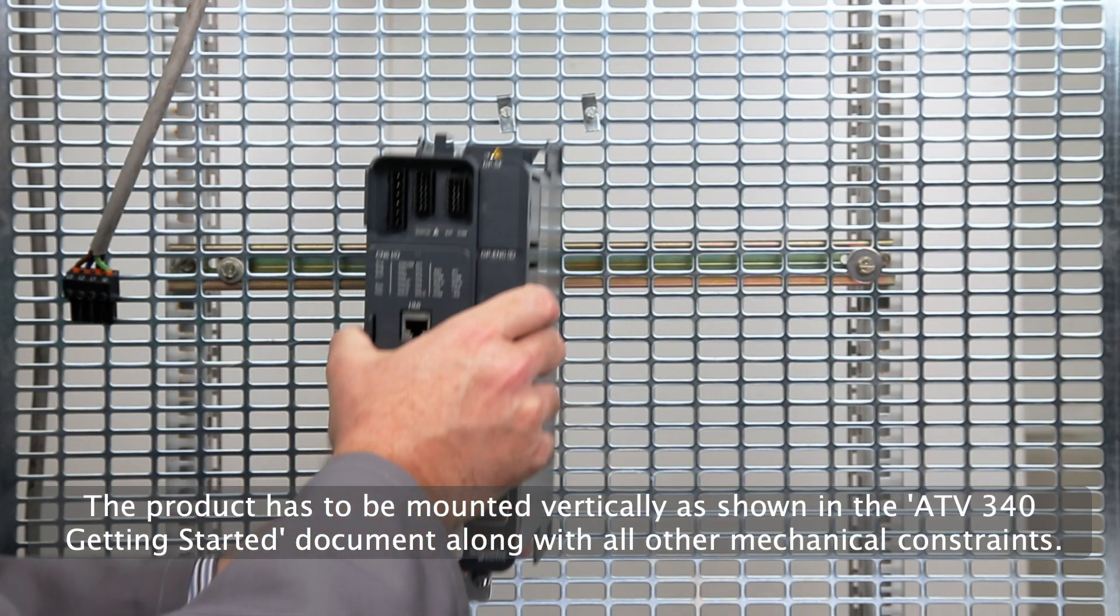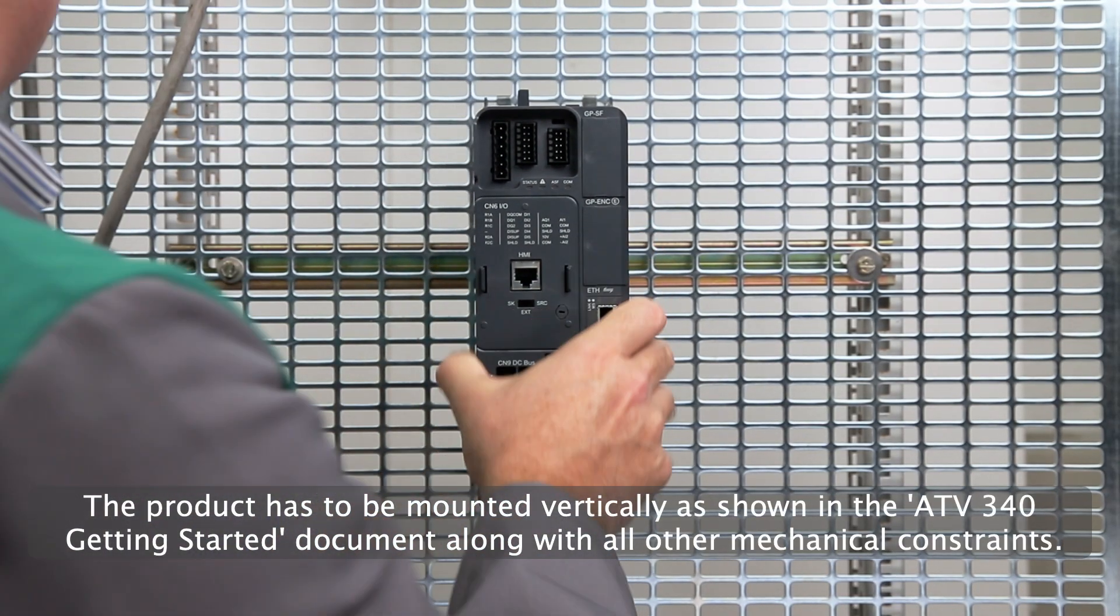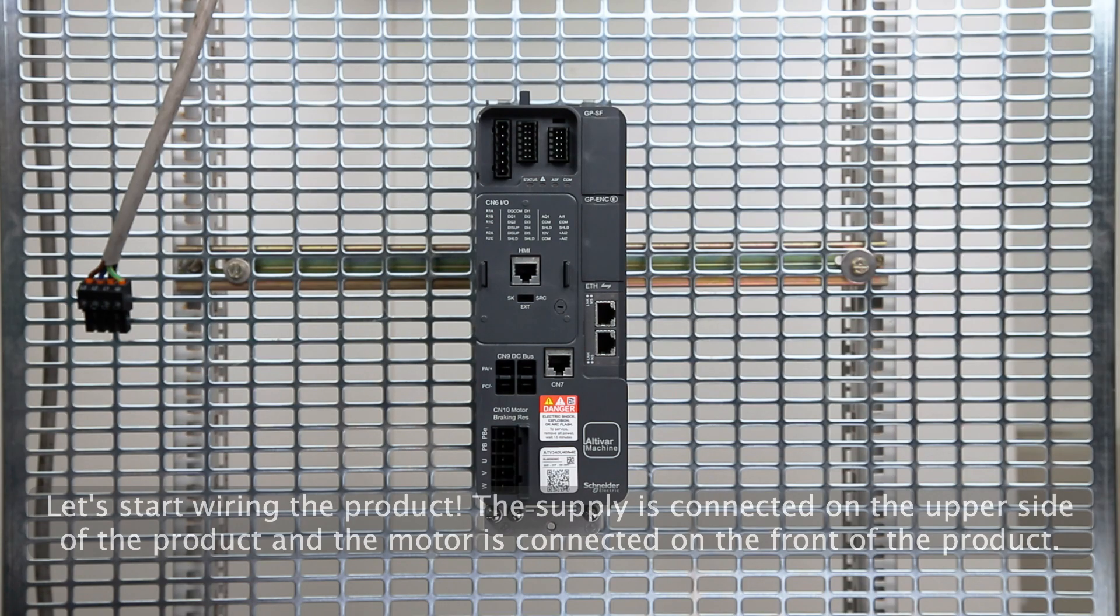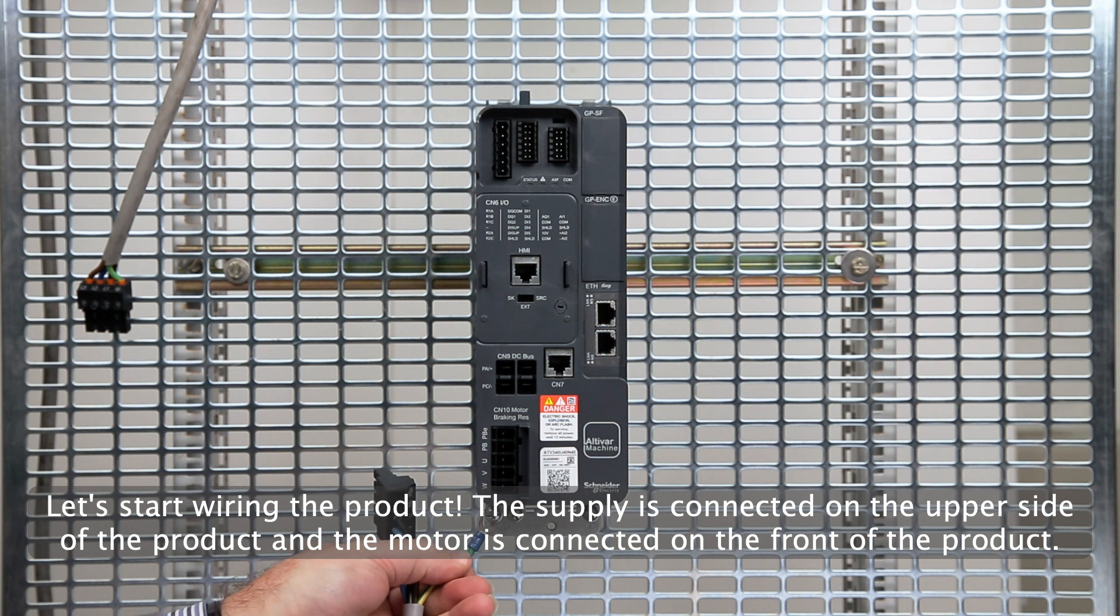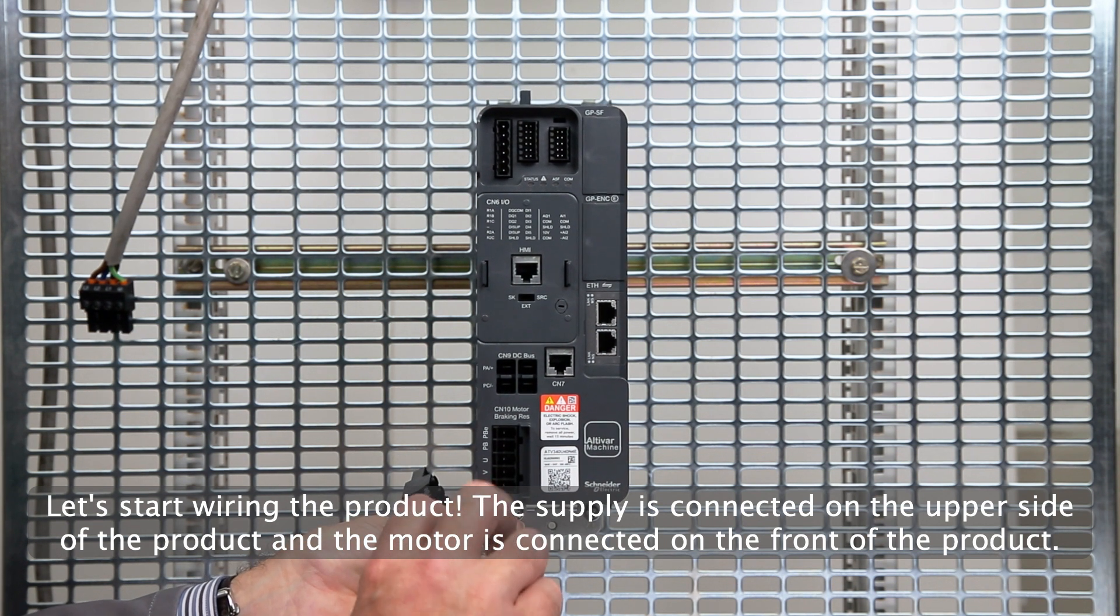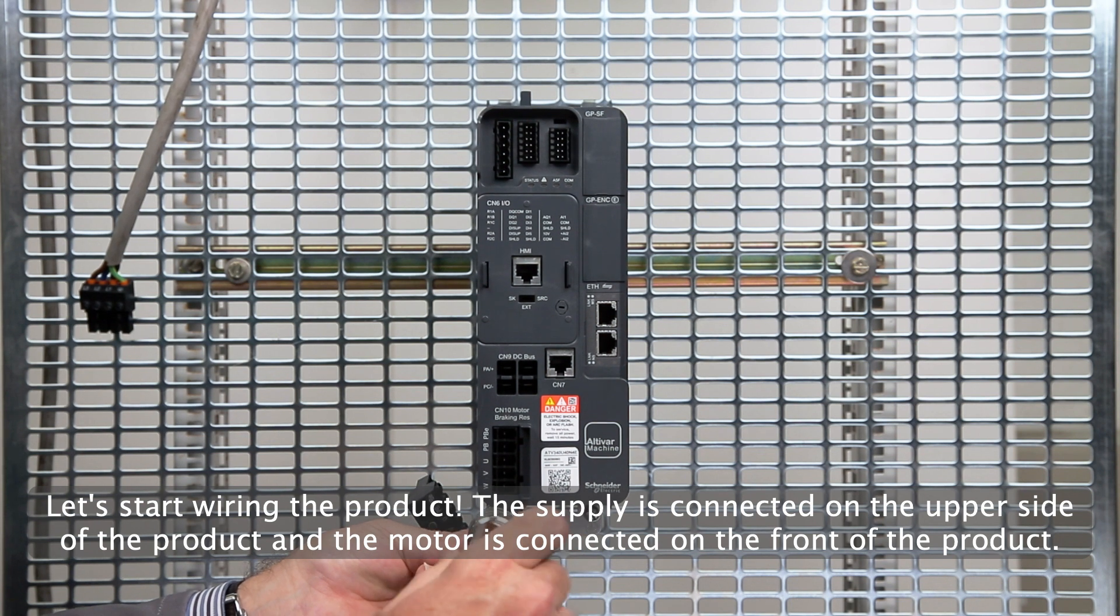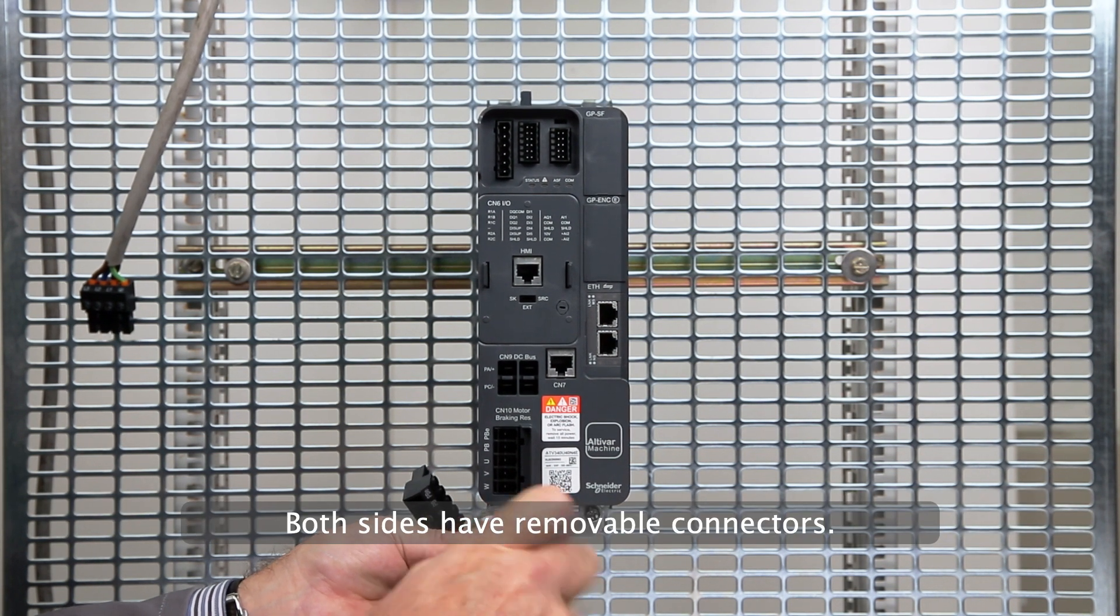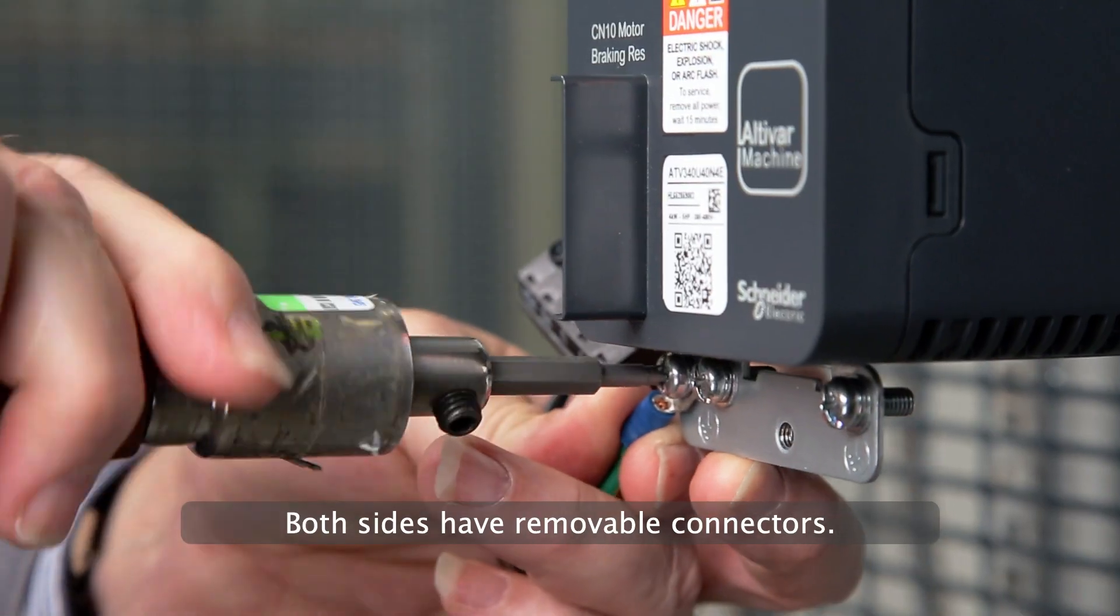The product has to be mounted vertically as shown in the ATV340 getting started document along with all other mechanical constraints. Let's start wiring the product. The supply is connected on the upper side of the product and the motor connector is connected on the front of the product. Both sides have removable connectors.